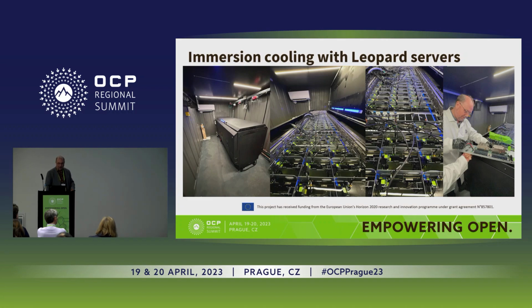Then we threw all these servers into an immersion system, and some of you may recognize which immersion system that is. But here you have 2 power shelves sitting in, and there's 2 bus bars at the bottom. So there's 2 12-volt bus bars at the bottom of the tank, and we've got 54 of these OCP servers in the tank, 27 on one bus bar and 27 on the other. And so the power is converted in the tank and then supplied to the 54 servers.